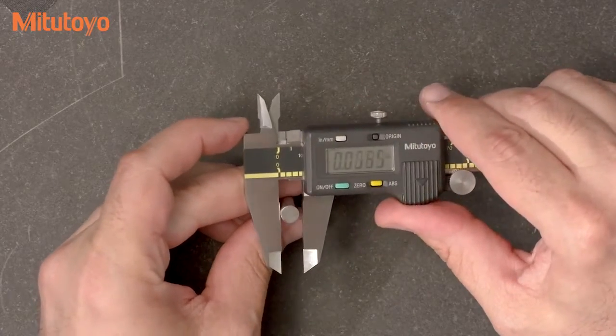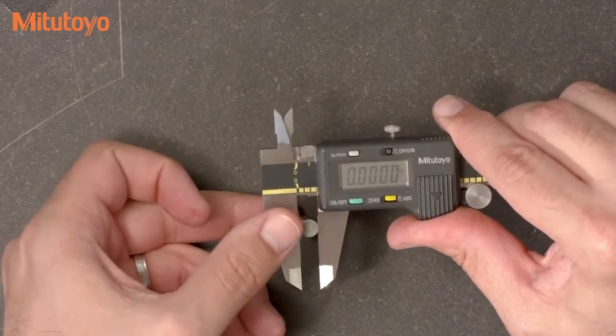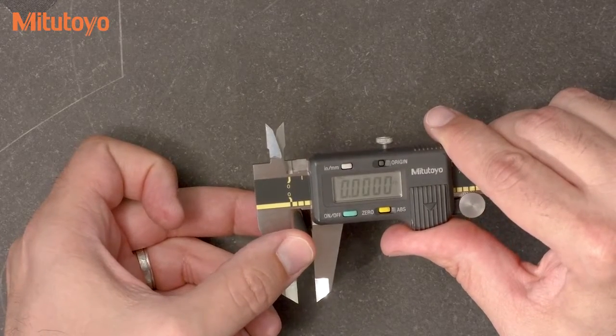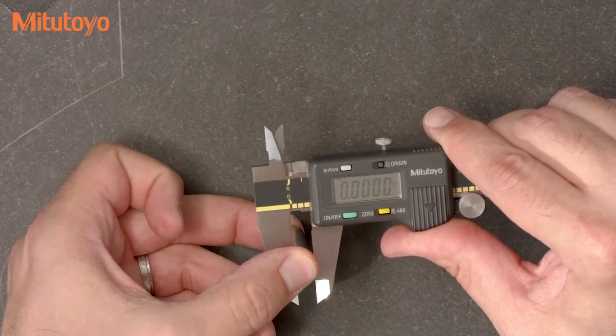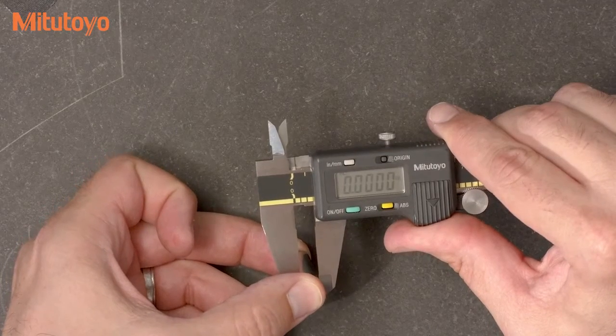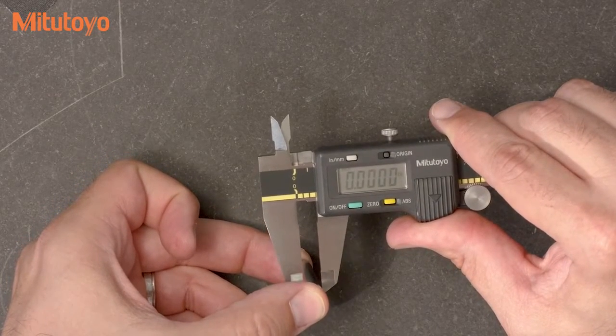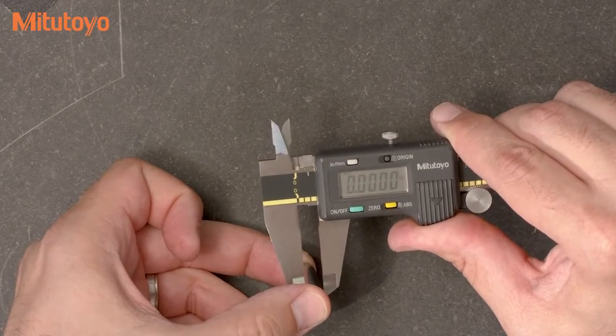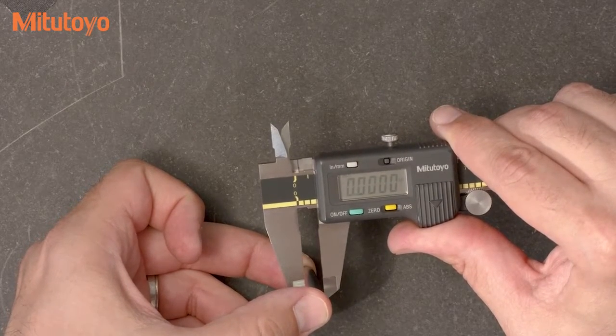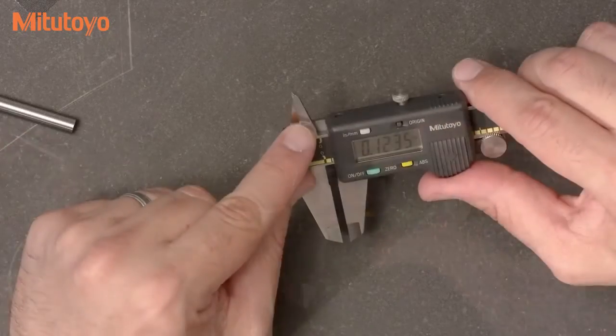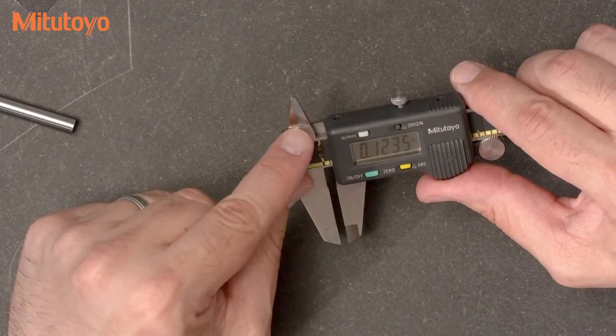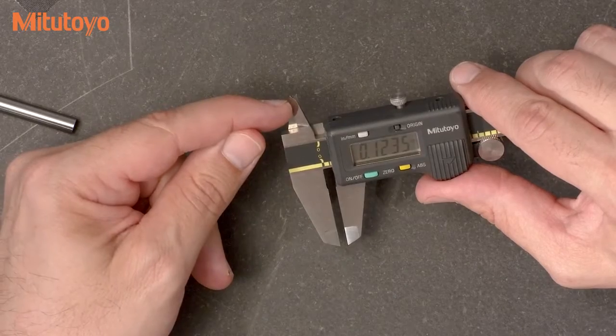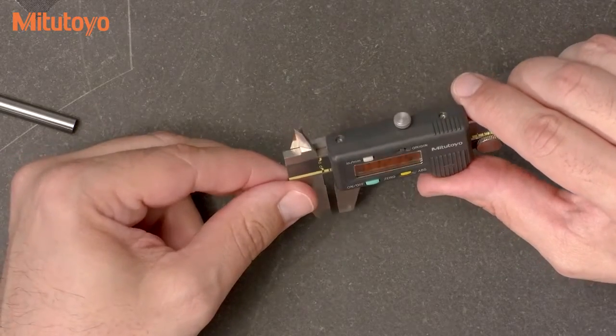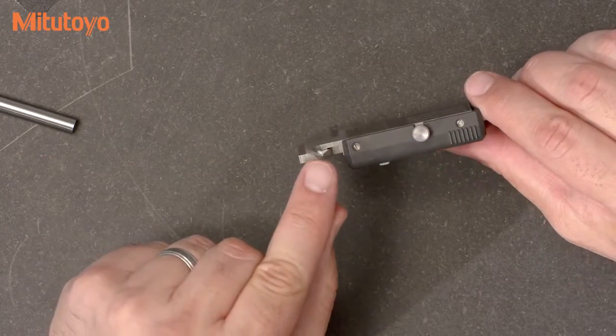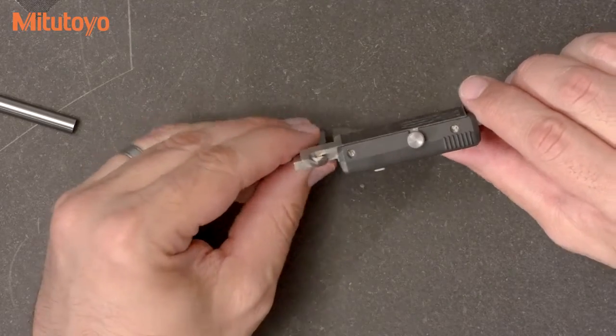This is done by simply moving the gauge pin from near the beam to the tips of the jaws while observing the readings. Here all the values are 0, so we know that the flatness and parallelism of the jaws are in good shape. The use of a light gap is also good for checking the condition of the internal measuring faces, in particular when you have the crossed knife edge type like we have on this caliper.